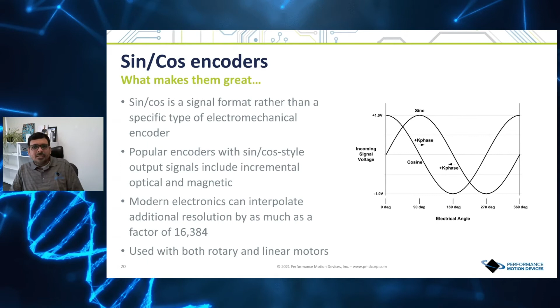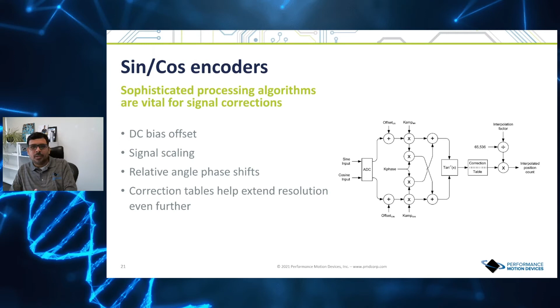Here's a bit more detail on the Sine Cosine encoder—good for you to go back to as a reference, and we'll provide these slides. You get a sine and cosine input, then you run an algorithm: you do an arctan, apply a correction table, and then the interpolation factor is applied to derive the actual position.